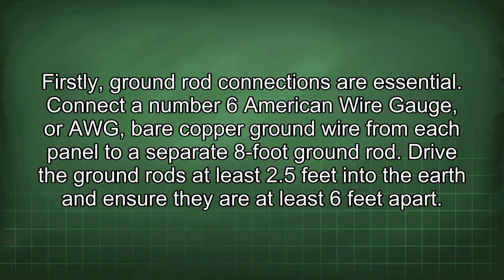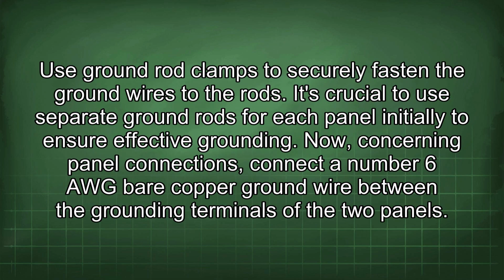Firstly, ground rod connections are essential. Connect a number 6 American wire gauge, or AWG, bare copper ground wire from each panel to a separate 8-foot ground rod. Drive the ground rods at least 2.5 feet into the earth and ensure they are at least 6 feet apart. Use ground rod clamps to securely fasten the ground wires to the rods. It's crucial to use separate ground rods for each panel initially to ensure effective grounding.